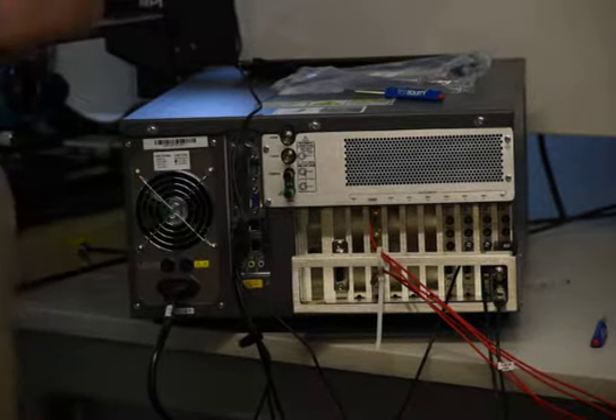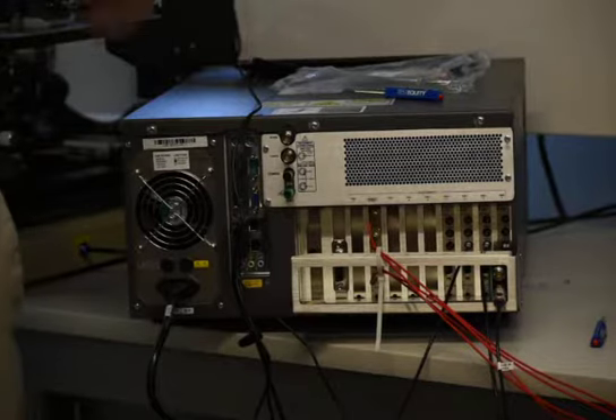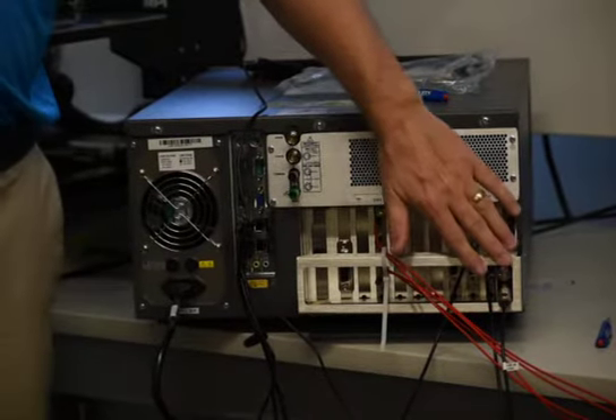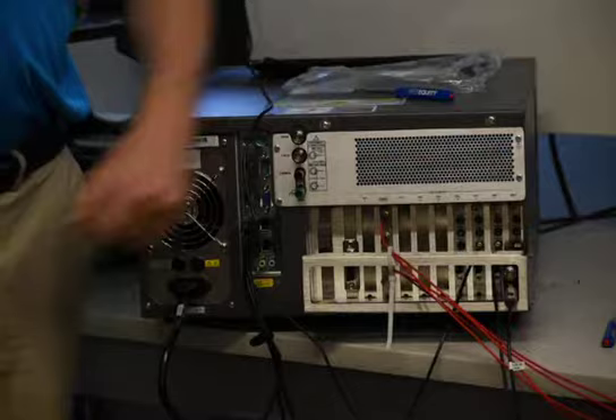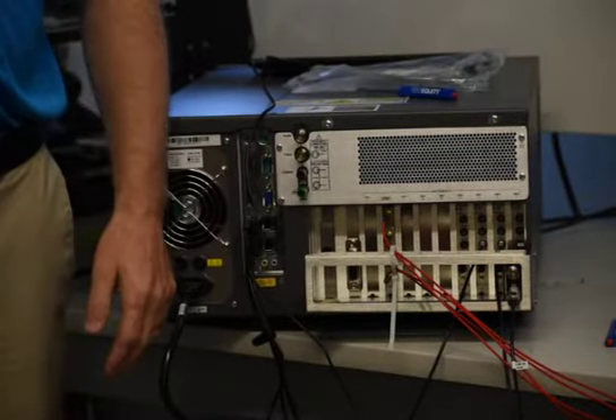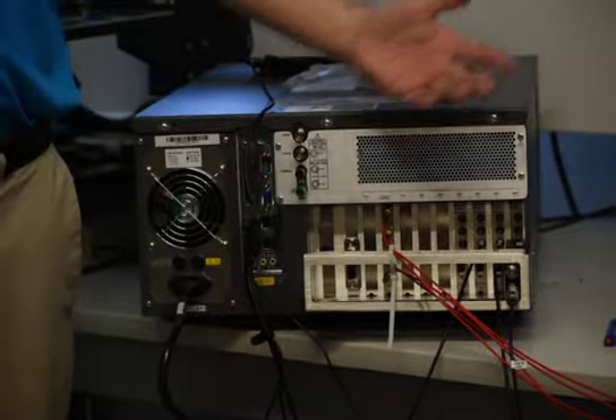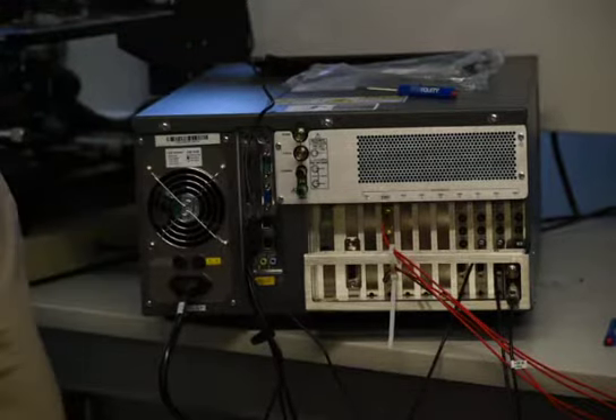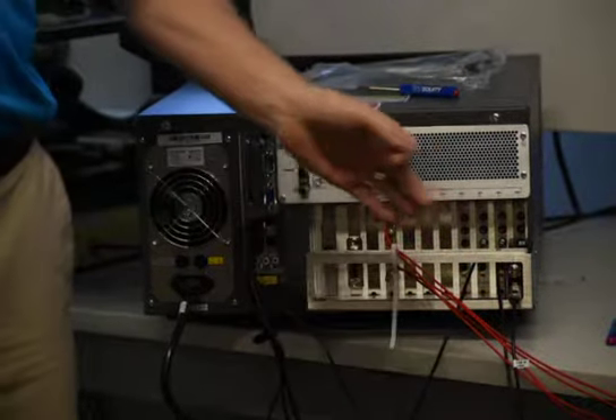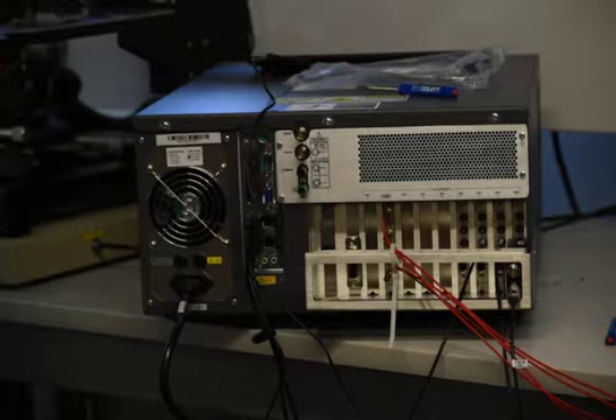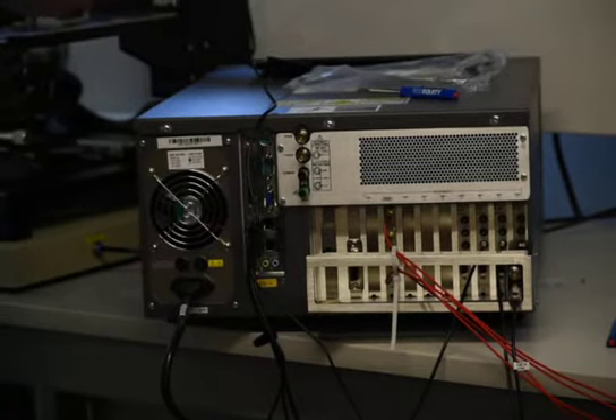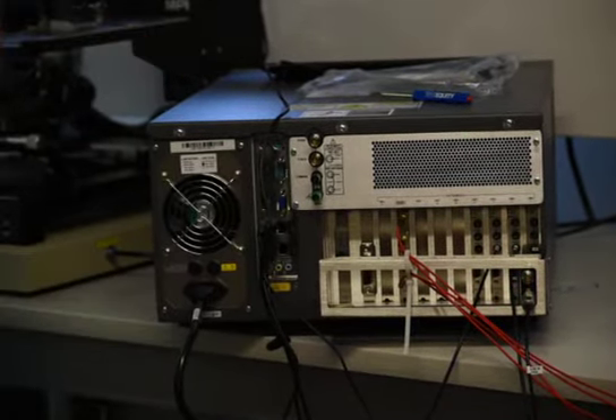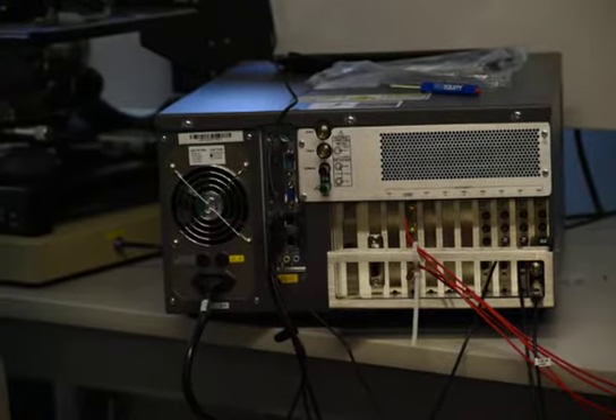So the deal is, the best performance you're ever going to get out of a piece of equipment is right out of the back of the instrument, right? Anything you attach to it from there, you degrade your capabilities. That's just the way it is. Every single connector, every adapter, every cable, every inch of cable, you're reducing your capabilities to make good measurements every time you add something to it. So the less things you can add, the better.